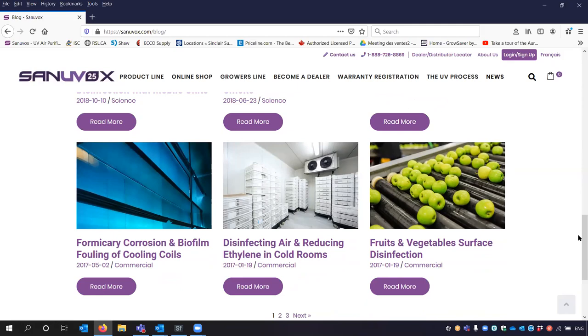So when we look at ductwork, we always recommend using aluminum because it's highly reflective and enhances the UV treatment dosage. If we're looking at galvanized steel, it has very low reflective qualities, only about 25% reflective. So that will affect the sizing of the duct and the dosage treatment.